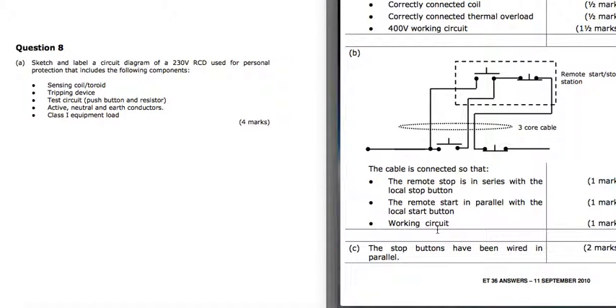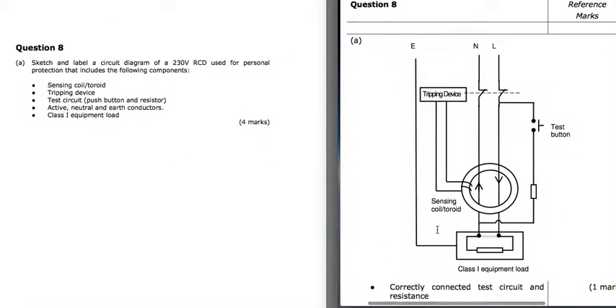Question 8, we're looking at an RCD. In the previous paper there was a 3-phase RCD. This is just a single phase RCD, so nice and easy. Got your toroid, your phase and neutral, your live and neutral going into your load. Test button between the live and the neutral with a resistor in there to limit the current.